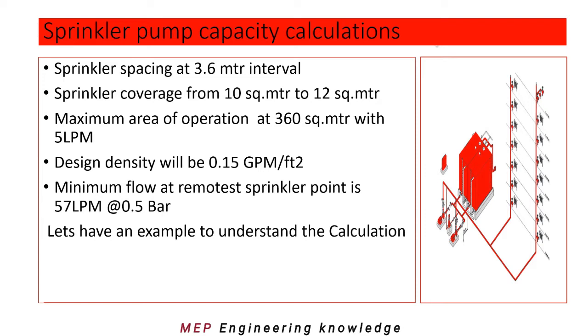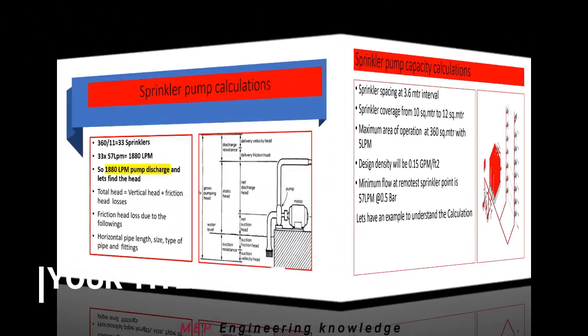As seen in previous videos, sprinkler spacing is maintained at 3.6 meter intervals with sprinkler coverage from 10 to 12 square meters. So the maximum area of operation is 360 square meters at 5 liters per minute. Design density will always be 0.15 GPM per square feet. The minimum flow at the remotest sprinkler point is 57 LPM at 0.5 bar.